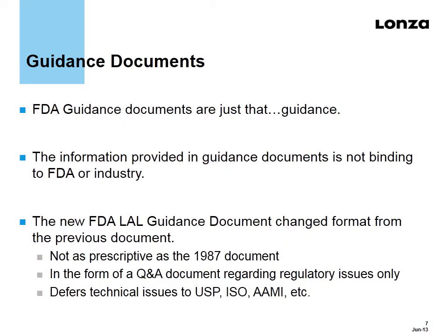Guidance documents. FDA guidance documents are just that, guidance. The information provided in guidance documents is not binding to FDA or to industry. The new FDA LAL guidance document has changed format from the previous guidance document. This document is not nearly as prescriptive as the 1987 document.